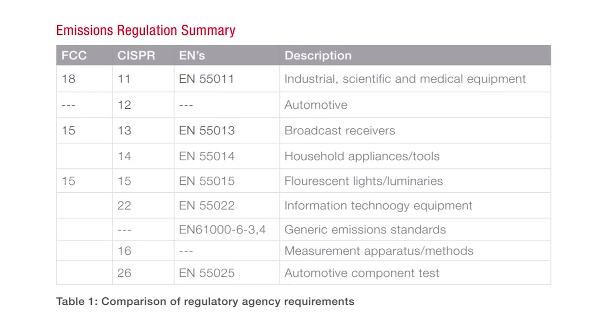Conducted emissions tests, on the other hand, characterize unintentional electromagnetic energy release via conductive material, like cables. So with this kind of test, you're testing for electromagnetic disturbances that are conducted outside the device along its interconnecting cables, like power, signal, or data cables. Conducted emissions tests focus on the unwanted signals generated through to the AC mains connection of a device. These emissions sources can include, but are not limited to, switches, regulators, and low-frequency clocks.